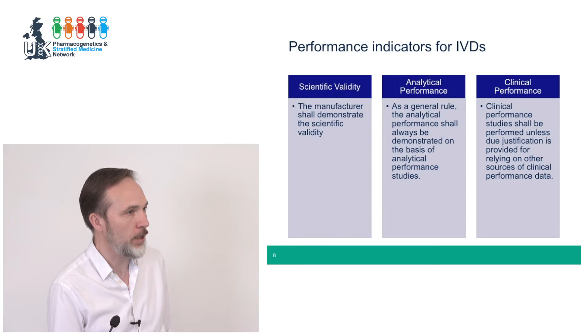And then clinical performance: clinical performance studies shall be performed unless there's a justification not to. And that may be because you can rely on other sources of clinical performance. So we need to have a think about what equivalence means there. Can you look at an equivalent device already available?